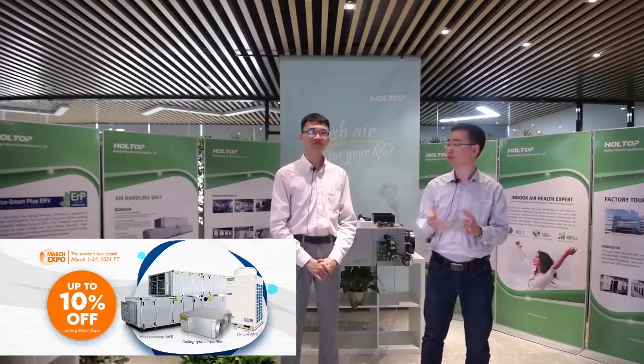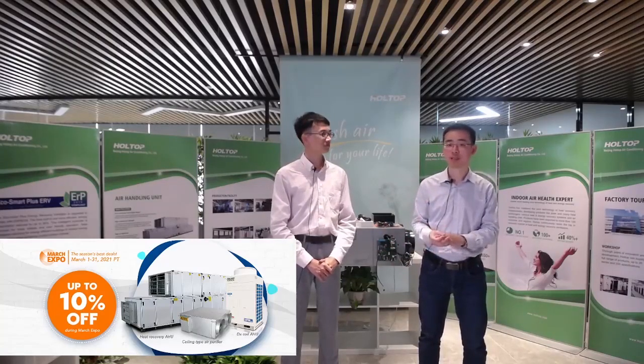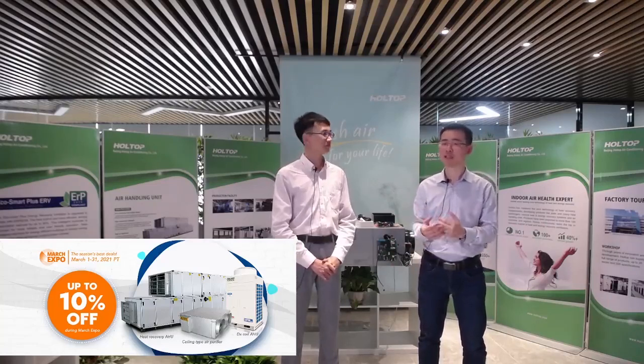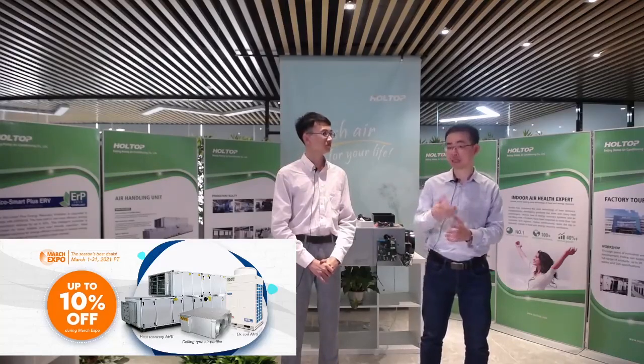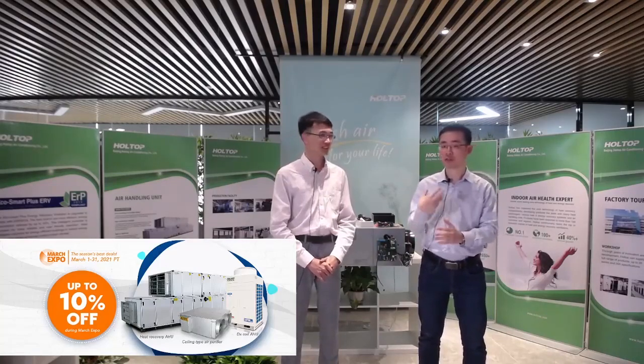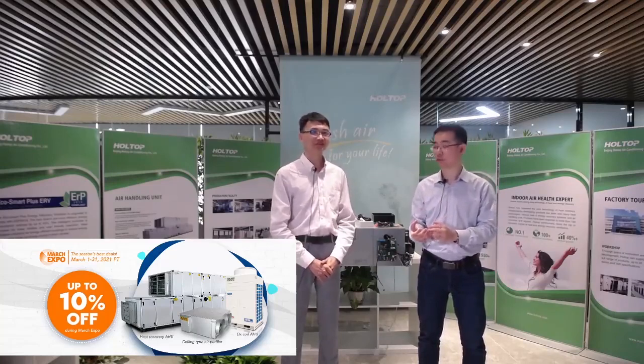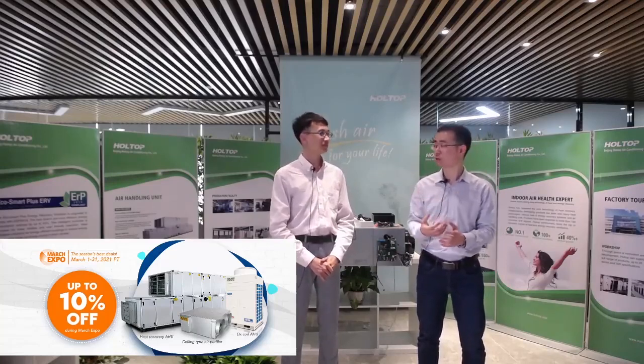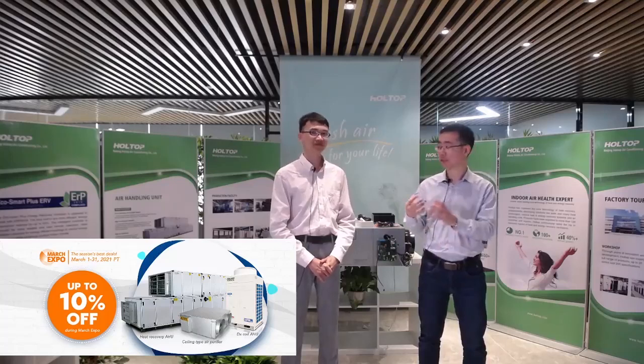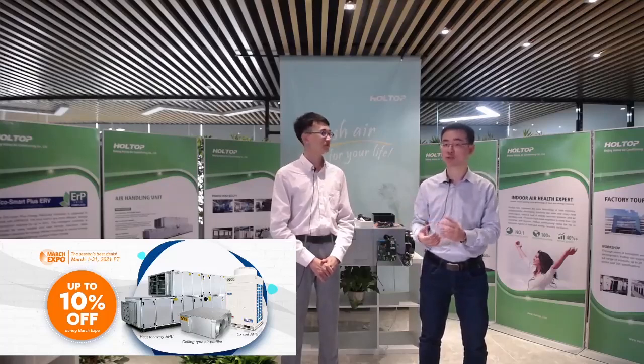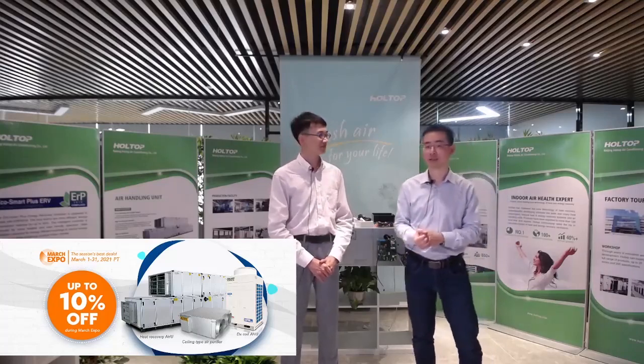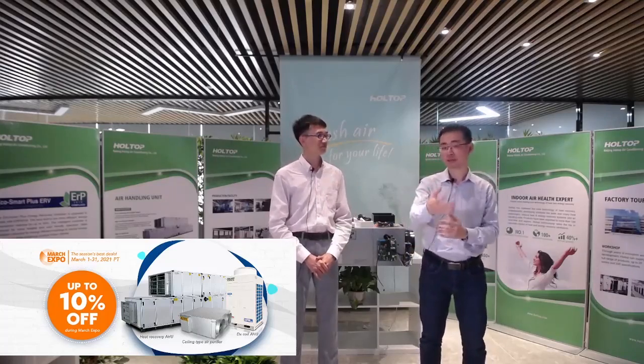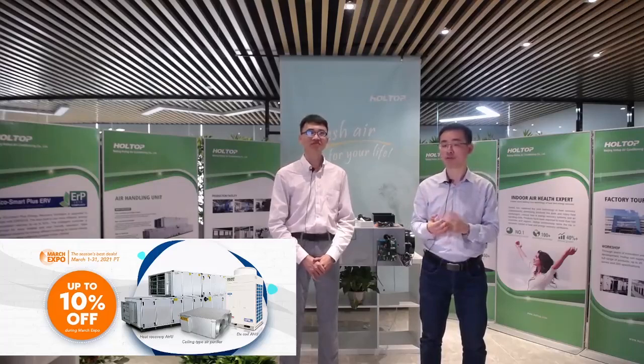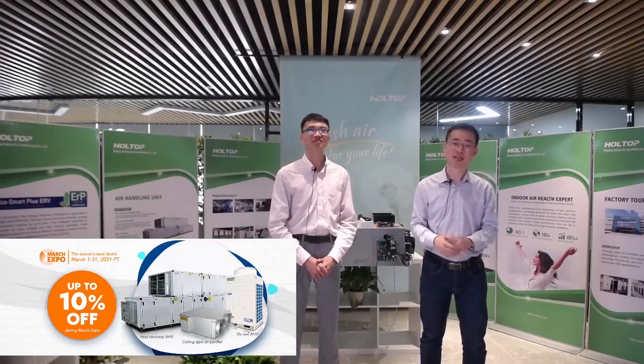Second, we need to calculate the cooling capacity for the fresh air, because as I know, in Sri Lanka the fresh air temperature is high, so the customer needs air conditioning to treat the fresh air before sending it to the room. A DX coil air handling unit with condensing units would be a good solution. We hope this friend can share more information about this project, and I'm sure our team will give you a satisfying answer.